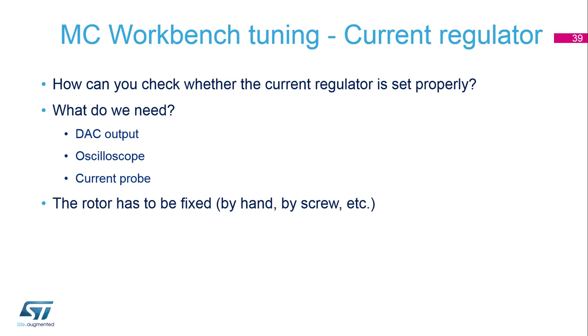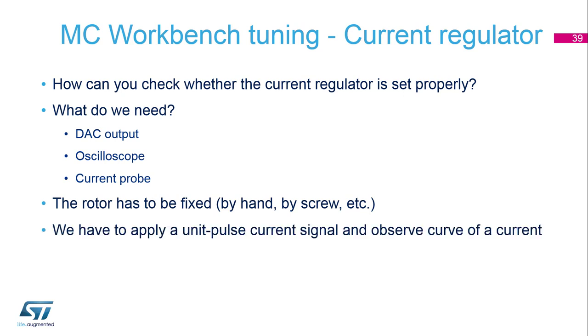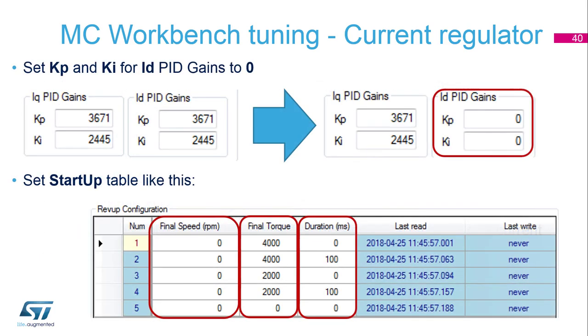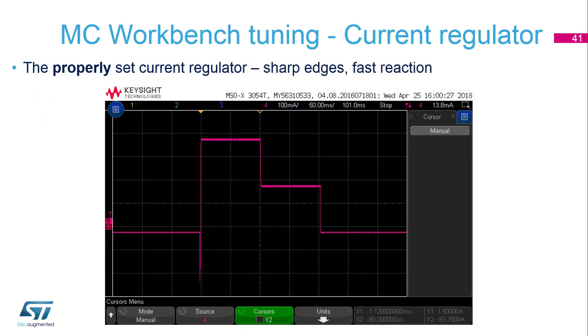A useful practice is to fix the rotor by hand or by fixing the load. We apply a unit pulse current signal and observe the resulting current curve. To do this, go to the monitor and set KP and KI initially to zero on the ID PI regulator, set up the startup table as depicted, and launch the motor. Then observe the current regulator response via the oscilloscope on the current probe and on the DAC outputs.